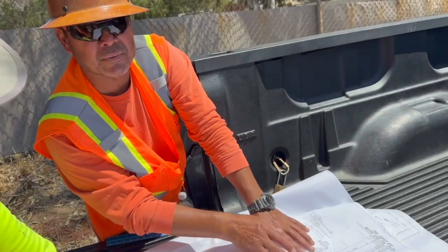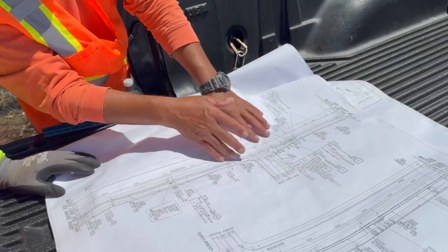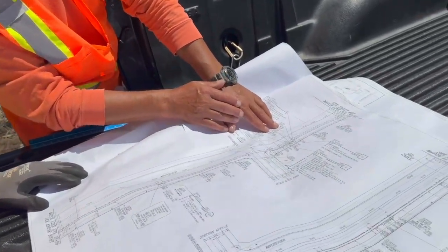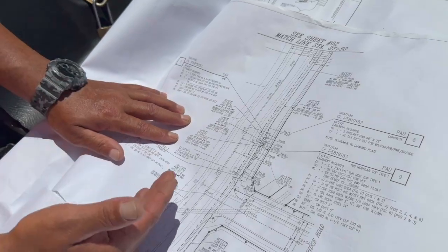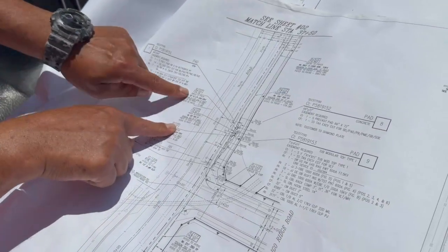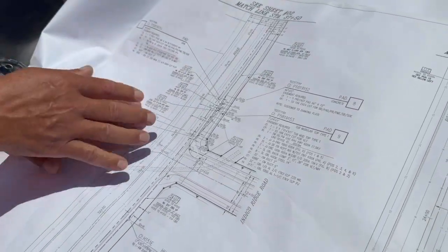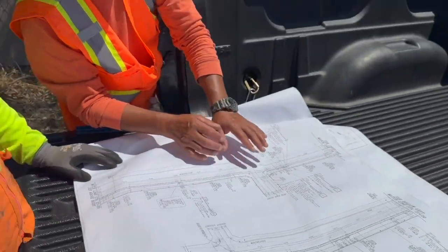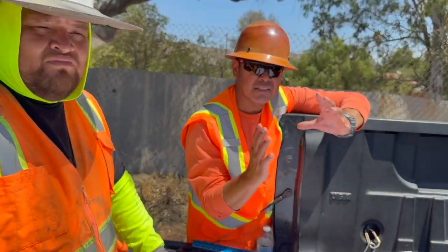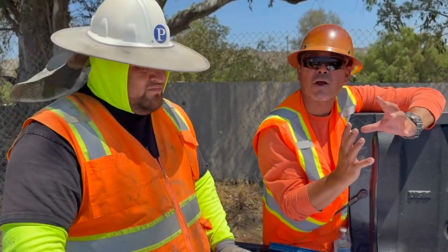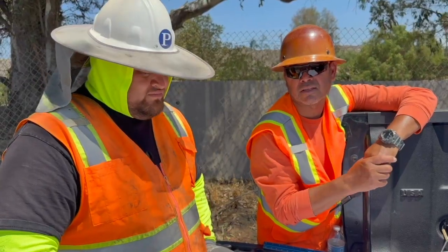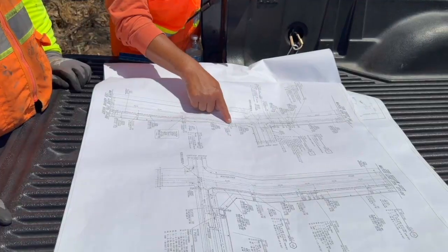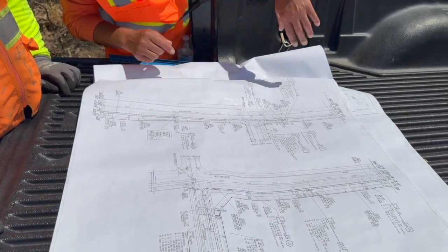If you remember when we were checking the single line, we just saw the blue line saying what kind of cable. Now they are telling us what kind of pipe they need to be able to feed that cable. Like in this one, you have a different measurement right there. So we need to put attention on each one and know which one is going in what direction. So those are little details. Like many say, they are a little more crowded, so we need to put more attention on it. And then just keep going with the callouts for the handholes, the runs, and the memo.